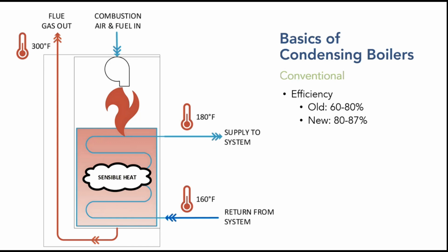Generally, for a newer conventional boiler, you're going to have efficiencies at 80 to 87%. If you're retrofitting, your boiler could be degraded over time. The heat exchange surfaces could be fouled up. Your burner controls could be out of whack. I mean, you could be operating at much lower efficiencies. So putting in a newer advanced control boiler, such as a condensing boiler, should be a significant efficiency gain.